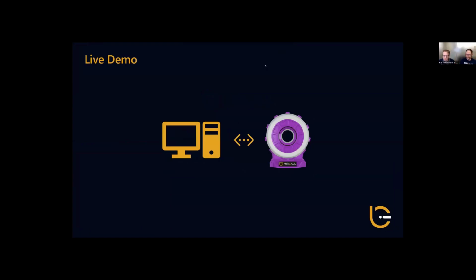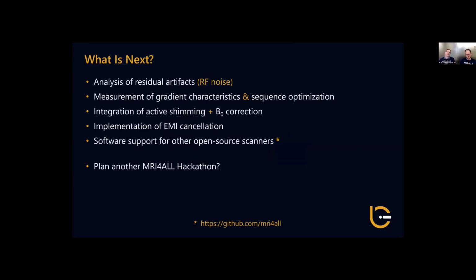It basically works, but of course, you've seen there are still some artifacts that we get. This is what we are currently working on. We are trying to analyze where these artifacts are coming from. We definitely still have problems with RF noise. We also noticed that we have very, very bad power quality in this building. It's a very old building where the scanner is located, and we get a lot of noise through the power lines.